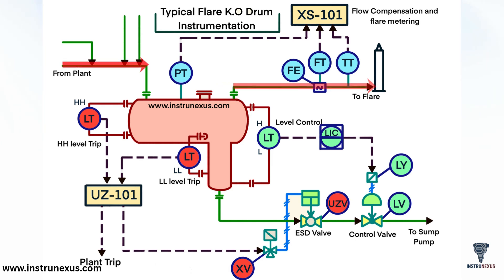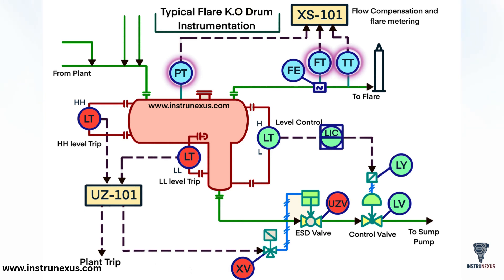On the outlet side, you can see flow instrumentation: a flow element (FE), flow transmitter (FT), and temperature transmitter (TT). These send signals to the flow compensation unit, XS101, which calculates the corrected flare gas flow rate for monitoring and reporting.